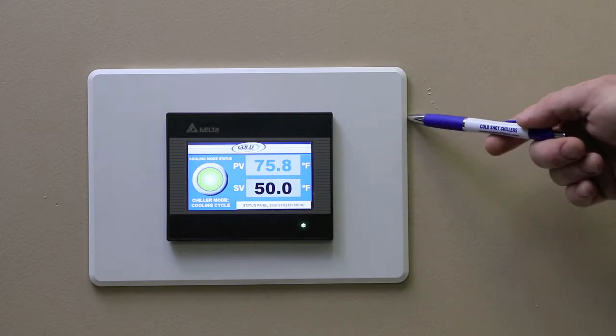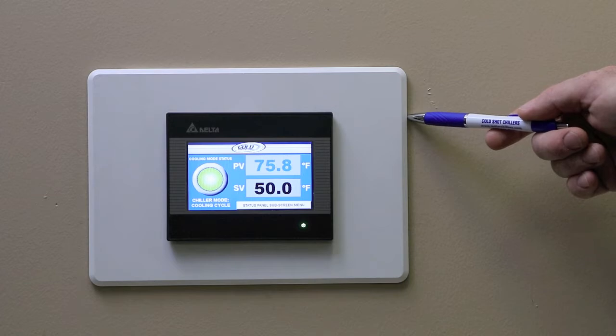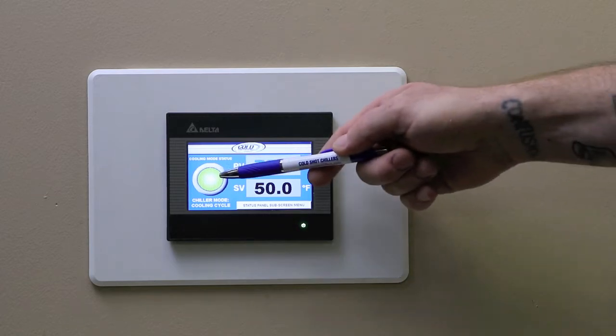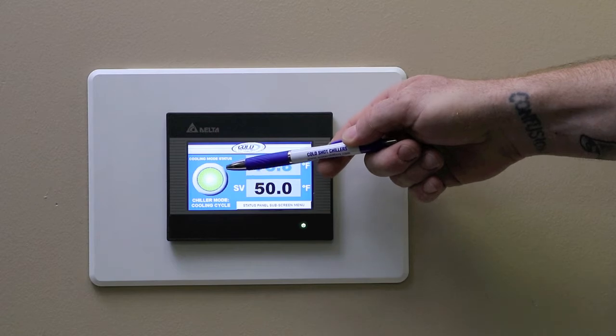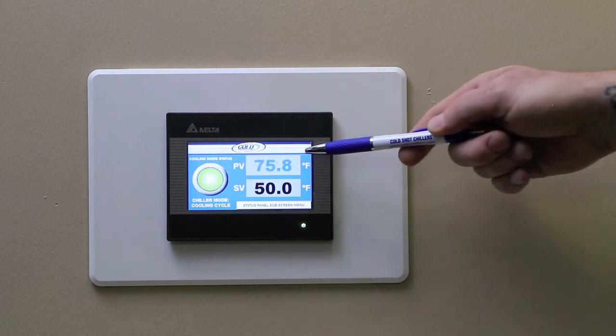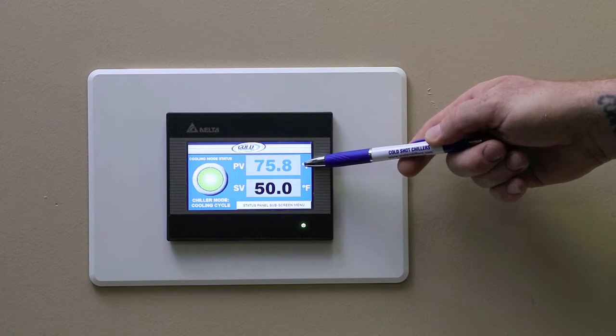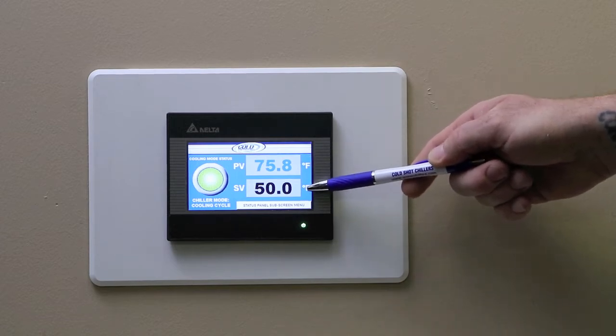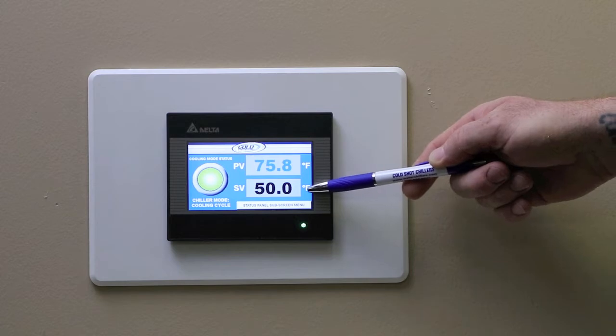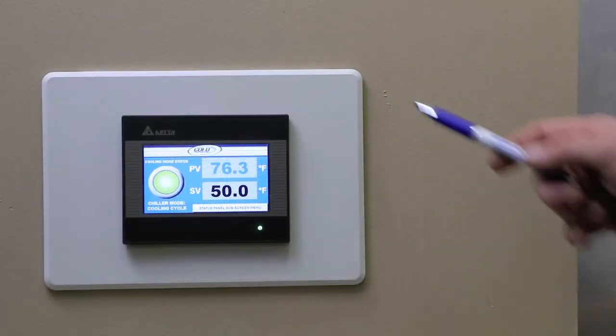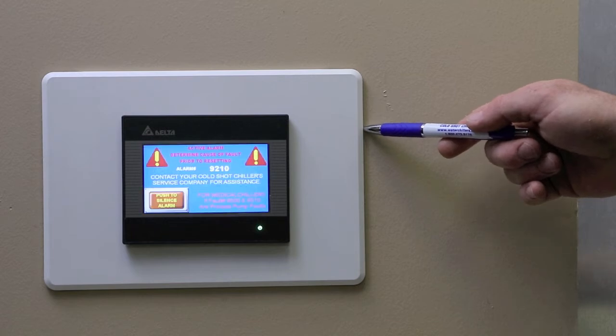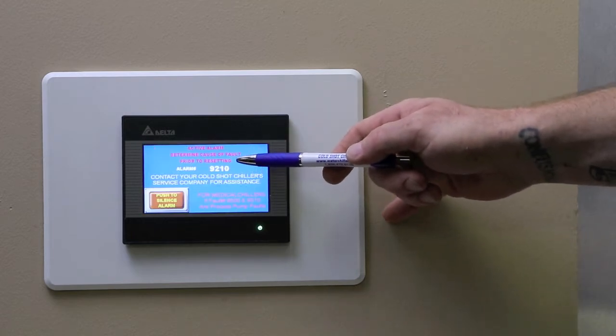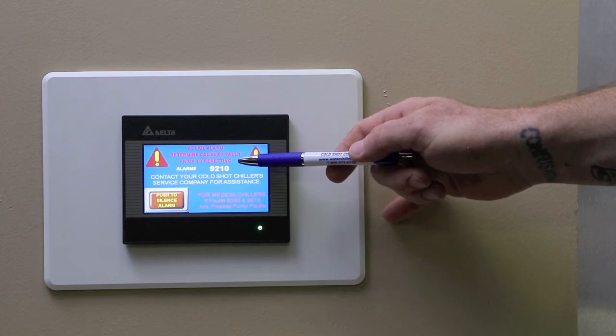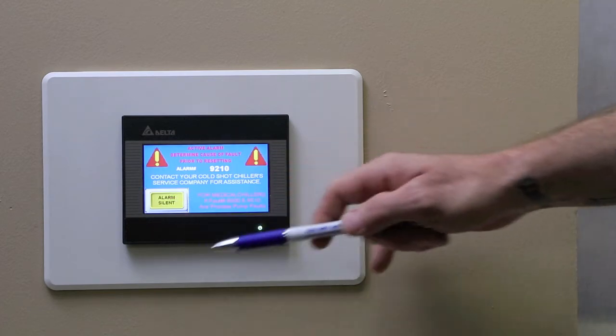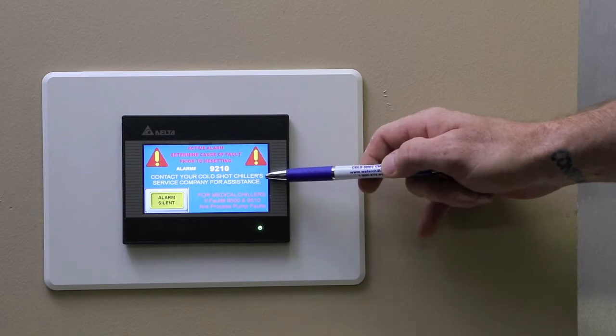This is the Cold Shot Chiller H2 remote status panel located inside of the building. The green light located on the left shows the chiller in normal working conditions. The PV process value tells you true temperature. The SV set value is what the chiller cools down to maintain that temperature. In the event of a problem, the panel will throw an alarm code identifying what safety has gone out on the chiller. Push the silence button to silence the alarm. Then proceed to call Cold Shot Chiller Service Company for assistance.